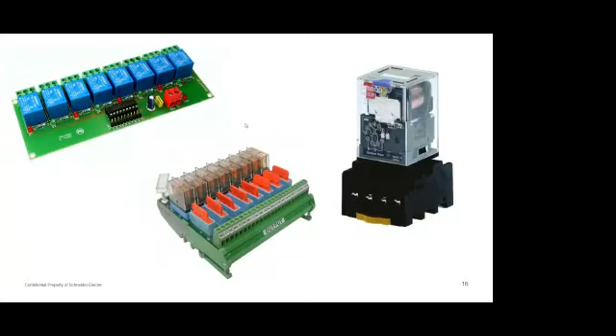So I told you about the solid state relay. The first drawing on the left hand side shows the solid state relay. These are quite expensive and used in various industrial automation applications like DCS and PLC systems. But there is a complication in using these devices. When they fail, the whole unit has to be replaced, or if it burns, the whole unit burns. It's quite expensive as well. So people always prefer to buy an electromechanical relay when the application doesn't require such a complicated or costly device.